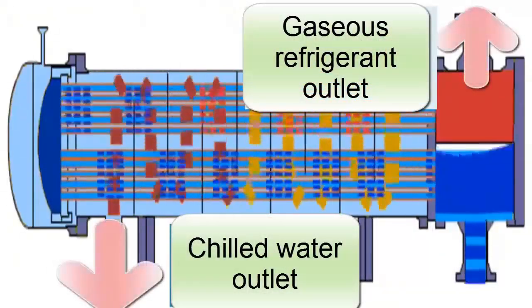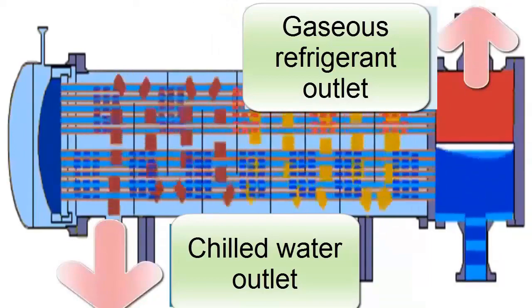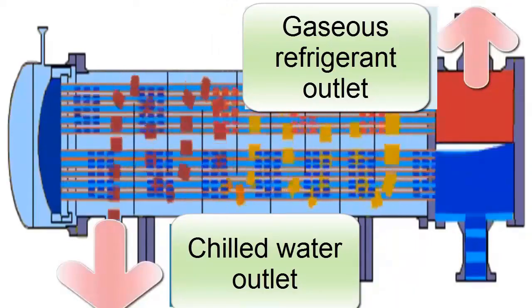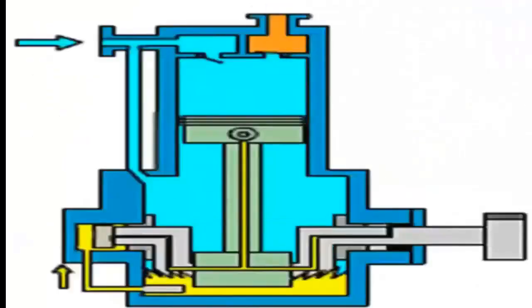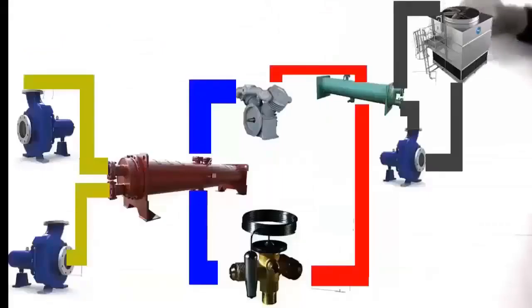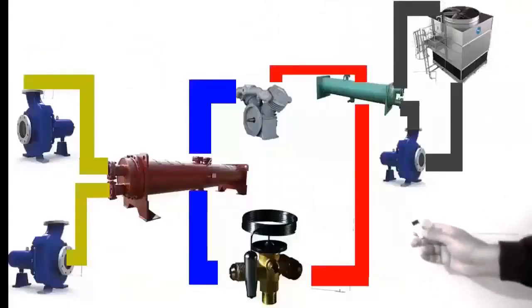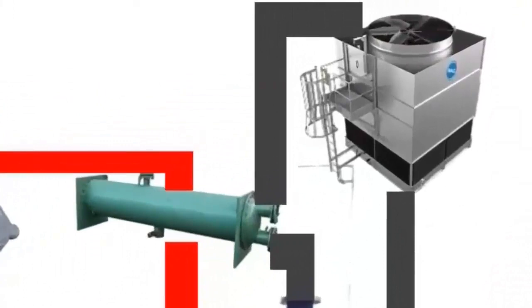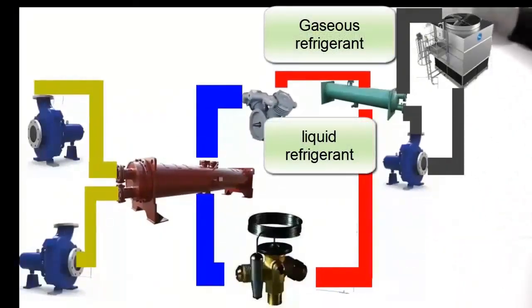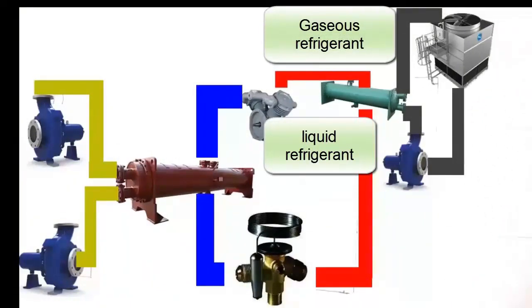So we have a phase change. In the evaporator, refrigerant enters in a liquid state and leaves in a gaseous, vapor state. That refrigerant is then subjected to compression by the compressor and sent to the condenser. In the condenser — which is what I am pointing to now — something quite important happens: the refrigerant arrives in a vapor state and we need it to return to its liquid state, requiring a phase change back.